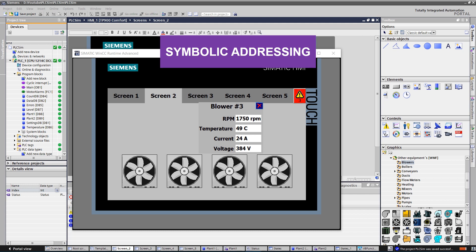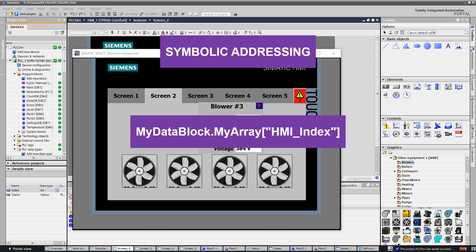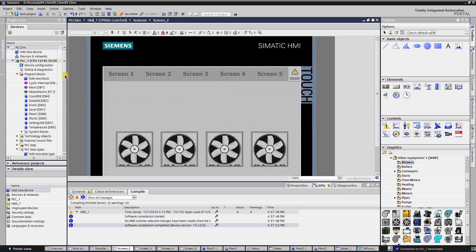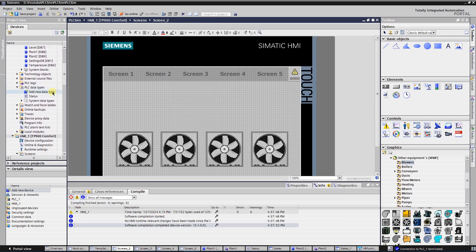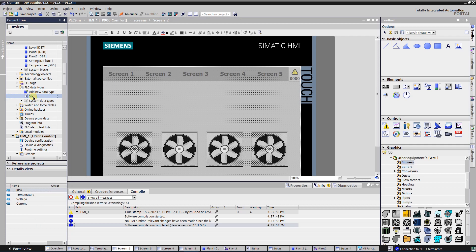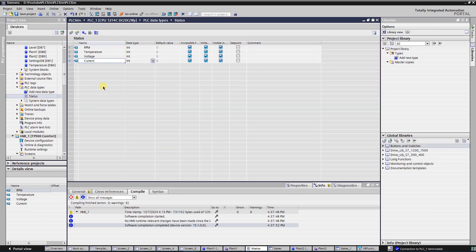Let's say you have a data block called 'My Data Block' and an array of tags named 'My Array' — then the expression for symbolic addressing would be as follows. The access to the index of the array elements can be controlled with the HMI tag, and the value of the HMI index tag can be supplied at runtime. Let's create a user-defined PLC data type with the RPM, temperature, current, and voltage readings of the blower.